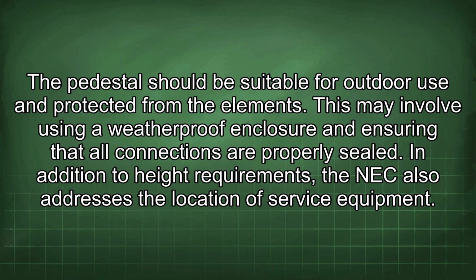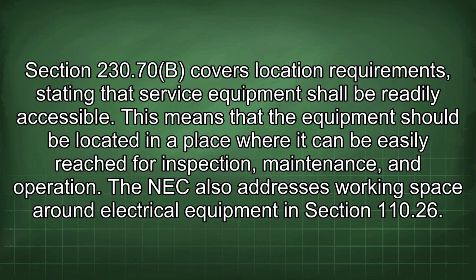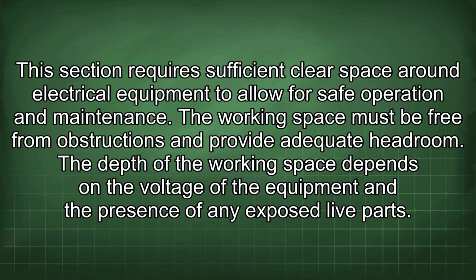In addition to height requirements, the NEC also addresses the location of service equipment. Section 230.70(B) covers location requirements, stating that service equipment shall be readily accessible. This means that the equipment should be located in a place where it can be easily reached for inspection, maintenance, and operation. The NEC also addresses working space around electrical equipment in Section 110.26. This section requires sufficient clear space around electrical equipment to allow for safe operation and maintenance. The working space must be free from obstructions and provide adequate headroom.